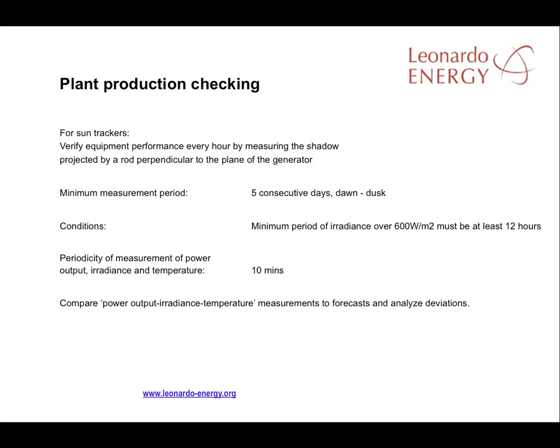In this slide you can find a suggested schedule for plant production checks. Measure every ten minutes for at least five consecutive days from dawn to dusk. That bank of data can be compared to the expected measures from the solar radiation maps or from the data from the meteorological station.